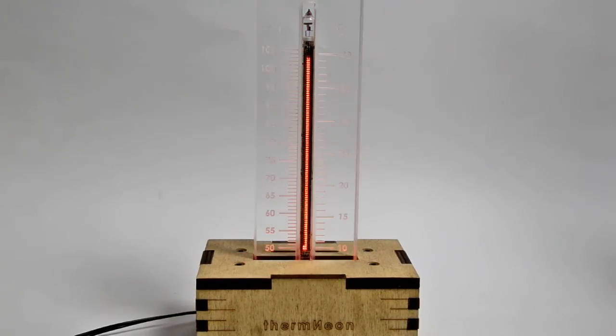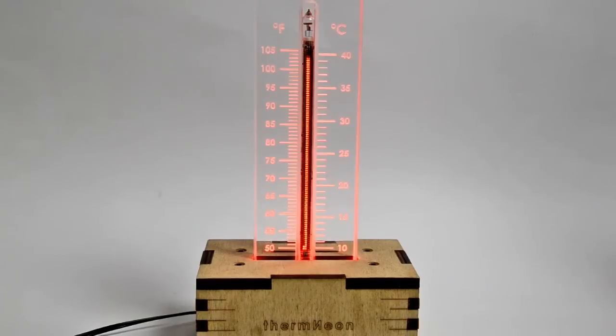Here, it is showing 40 degrees, which if you look in your manual at the table in section 7, 40 degrees for option 1 means the display duration of the temperature will be 60 seconds.